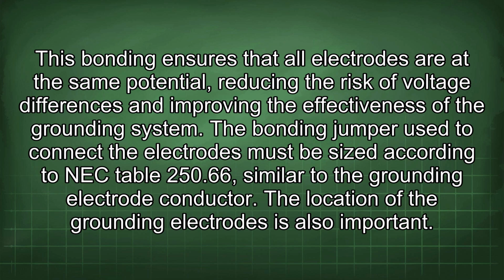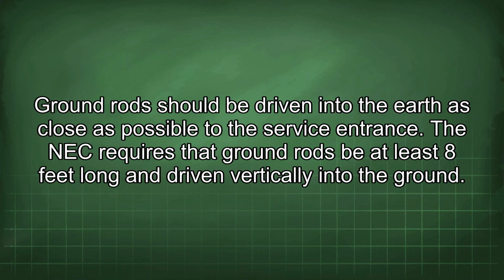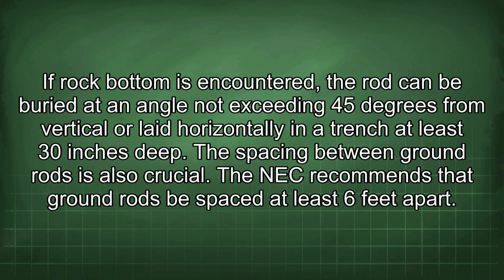The location of the grounding electrodes is also important. Ground rods should be driven into the earth as close as possible to the service entrance. The NEC requires that ground rods be at least 8 feet long and driven vertically into the ground. If rock bottom is encountered, the rod can be buried at an angle not exceeding 45 degrees from vertical or laid horizontally in a trench at least 30 inches deep.